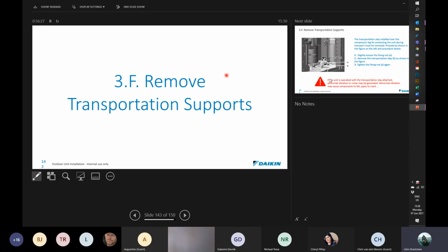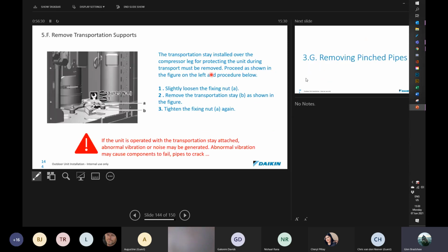So the next one is removing the transport brackets once the units are down and in their final location. Okay, the transport bracket can be taken out. This is usually yellow, unless it's been blue chemmed, then it will be blue. These need to be taken out, and then the bolts tightened down, but not tightened all the way. Again, you've only got to go basically one turn back to get it loose, and then no more than about 3 turns around. So don't go and tighten it down so that you squash the rubber. It just needs a couple of turns to take up the slack to make sure that there's no excessive movement.